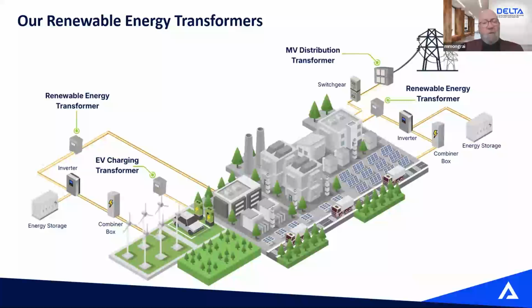So on a typical system, is the primary source more your wind farm or your building? Is it a system that will generate just a little bit, or a system that's going to generate a lot? If your main source of power will be your wind farm or your solar farm, then the taps should be on the proper side, if I could say. And if you use the building a lot to charge back your battery, in cases where the transformer is going to be used for a battery energy storage system, you want to make sure that you have your tap on the other side. Because if your building is at 600 but it's at 580, you still need to supply the right output voltage to your inverter, because if you don't provide the right voltage to your inverter, performance will drop. You can have a malfunction of your inverter.